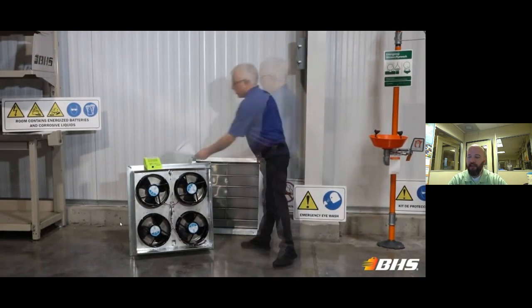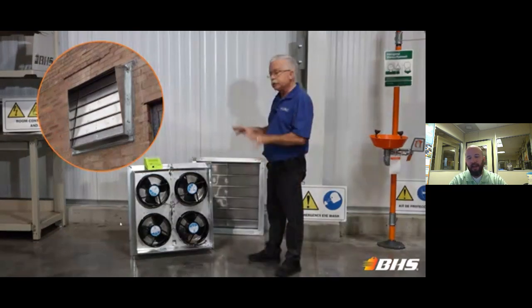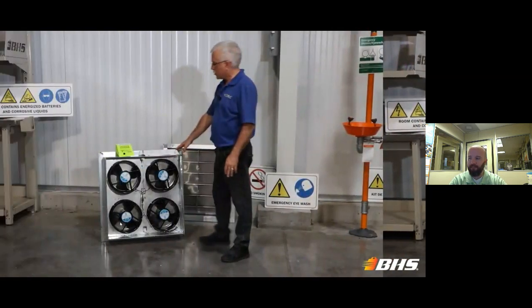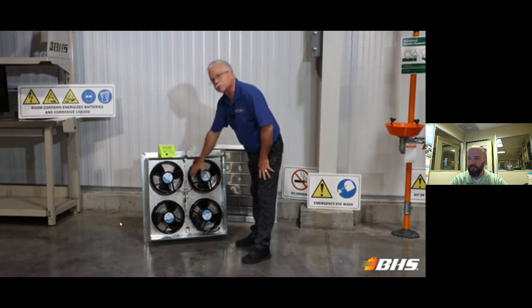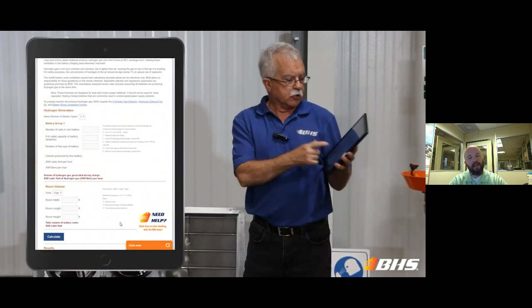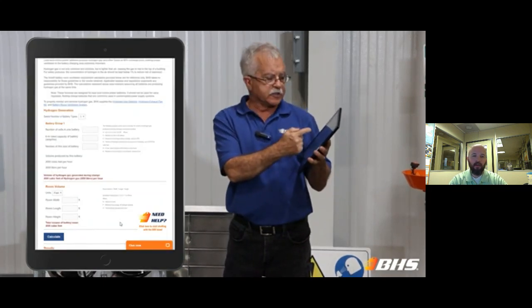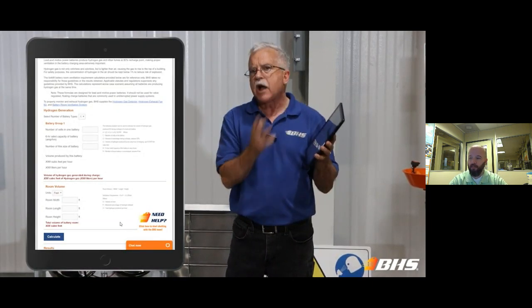You're showing the hydrogen exhaust fan kit, which includes the exhaust fan and a hydrogen gas detector all in one rooftop unit. With this hydrogen exhaust fan, there are 4 different fan motors, but the rating of the fan is based on the idea that if one of the motors were to fail, the other motors should still operate and are sufficient to ventilate the room itself.